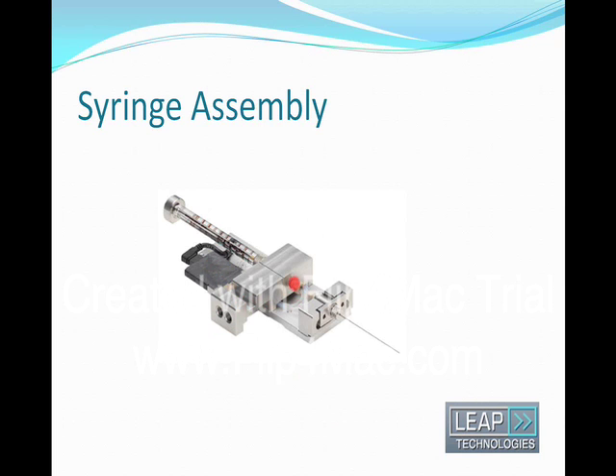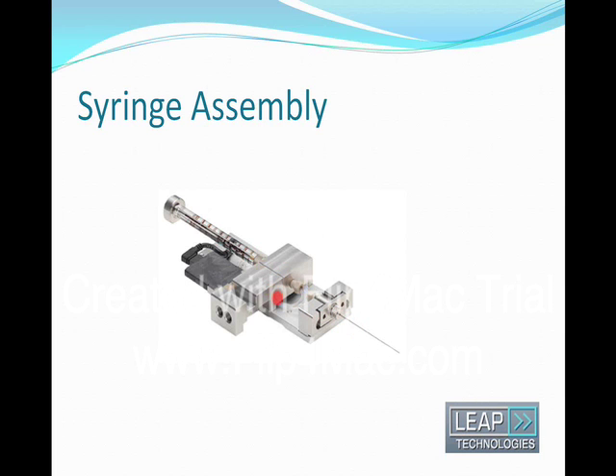If you look closely under this metal piece is the retention tubing. This isolates the needle, which is a removable needle, from the glass barrel of the syringe and is primed at all times. We'll see an animation of how this works in a few minutes. The retention tubing volume is just slightly larger than the volume of the syringe so that the sample never enters the syringe or makes contact with the solenoids.